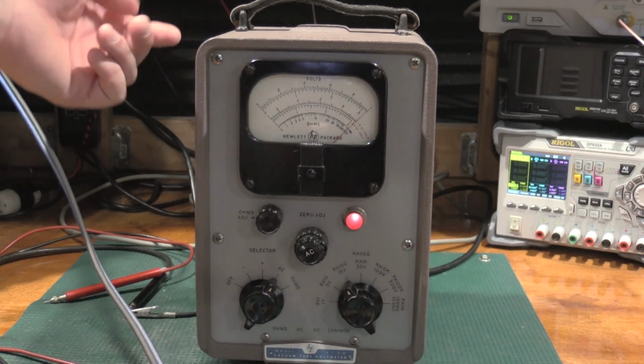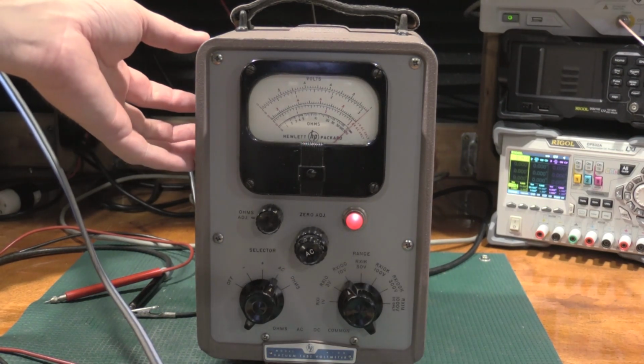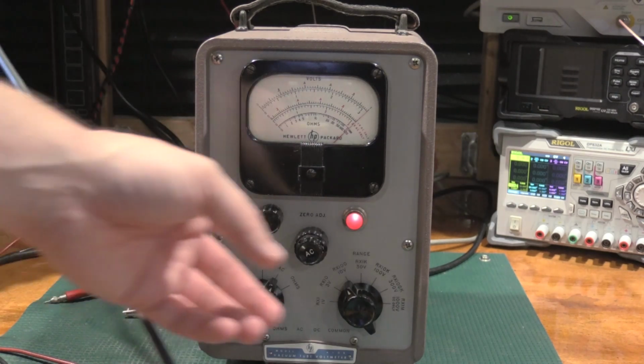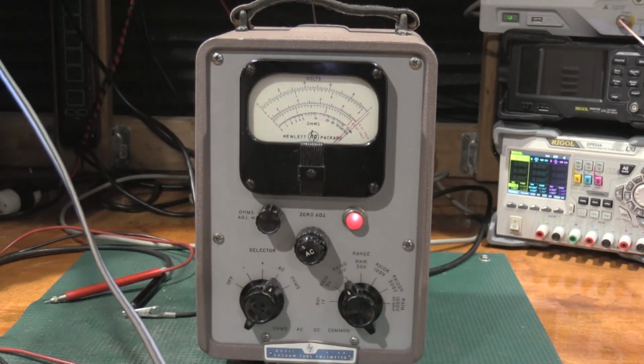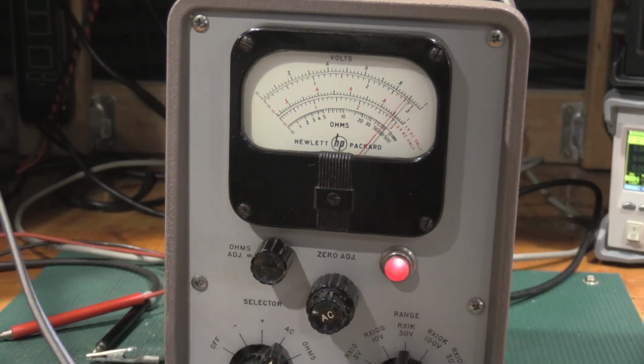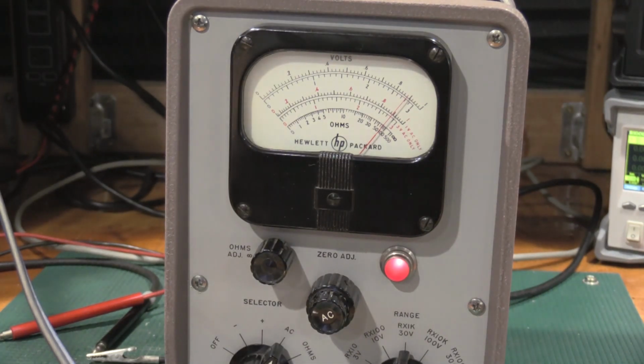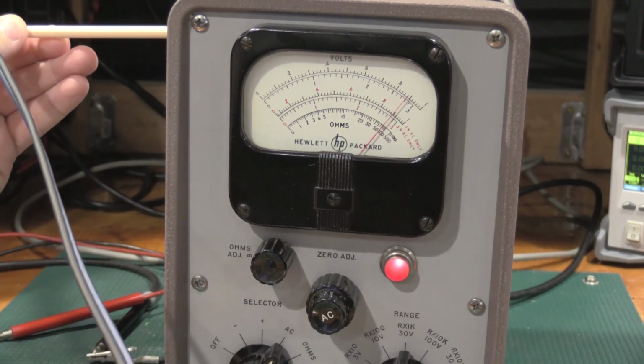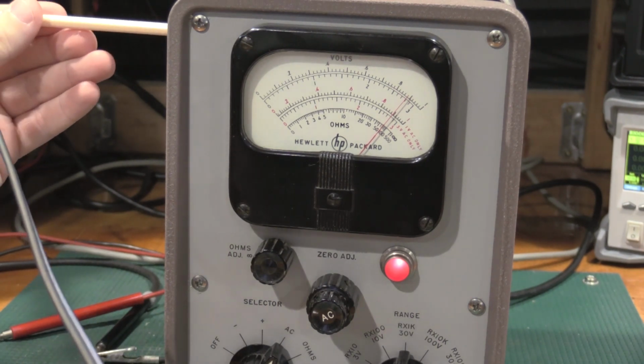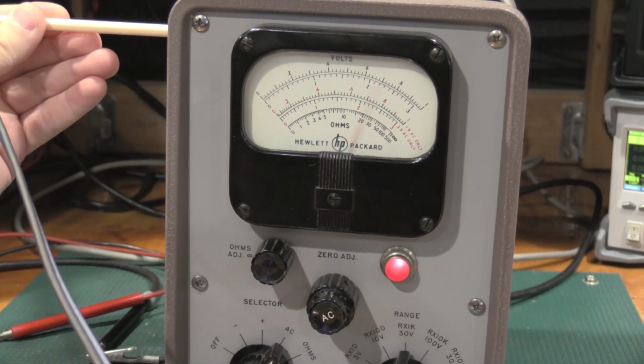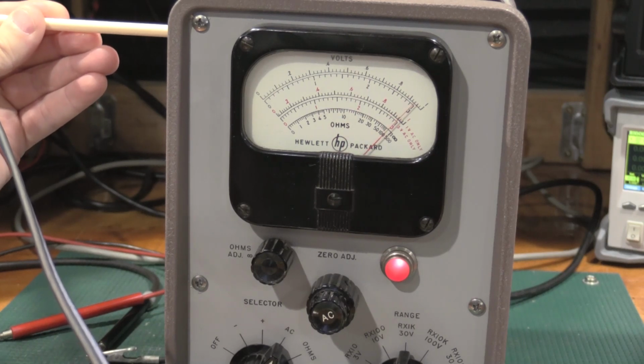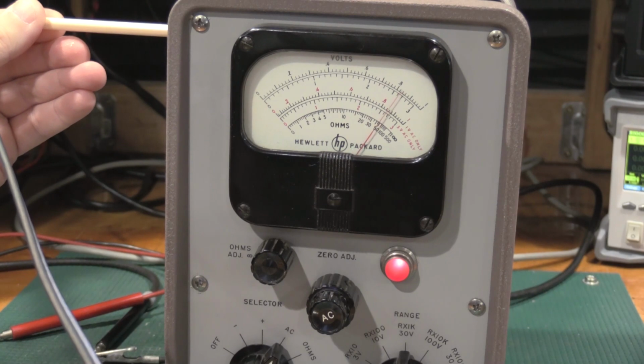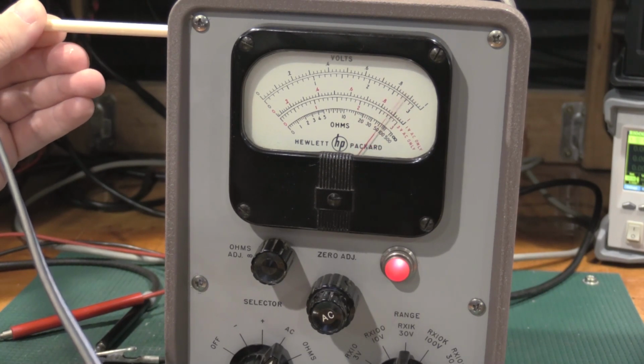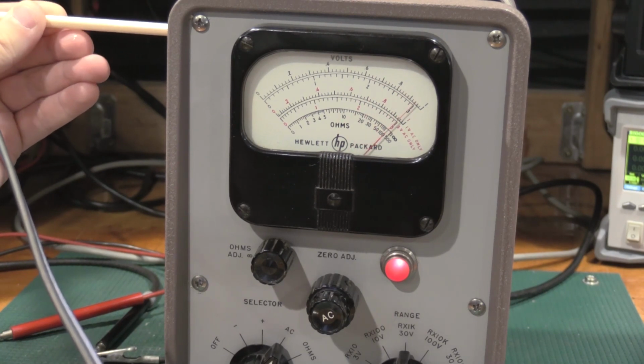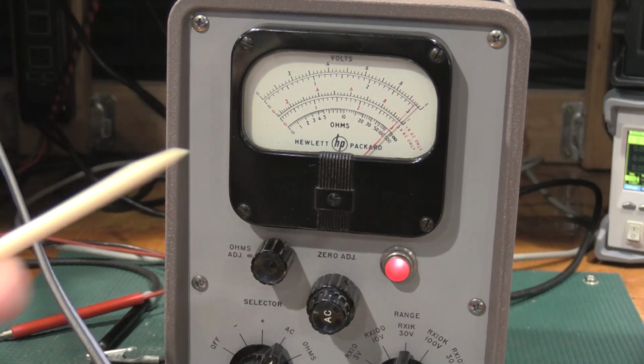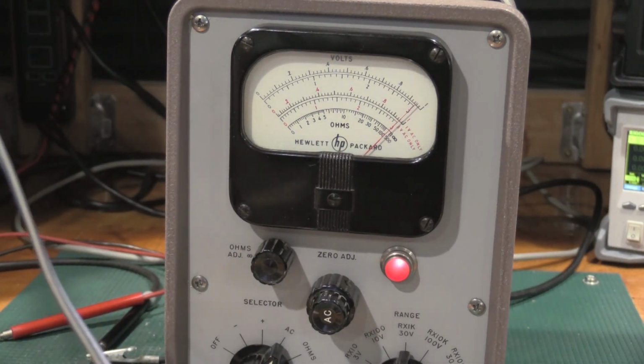Now the 30 volt range potentiometers are in the side of the unit, so I'll have to back it off of the case a little bit to do the 3000 and 300 volt range. And the 30 volt range is out a bit too, not surprising given the tube change, but we'll get right in here, bring this up to, and there we go, good for the 3 volt range.